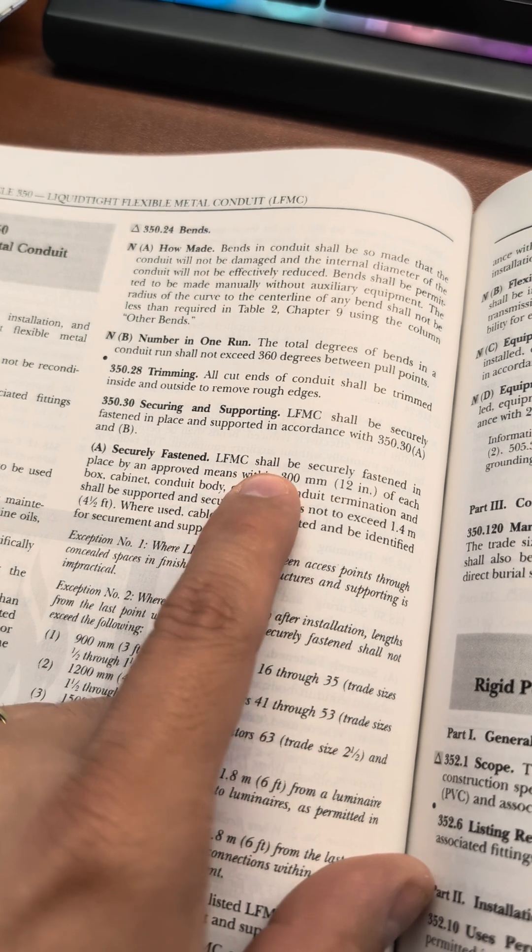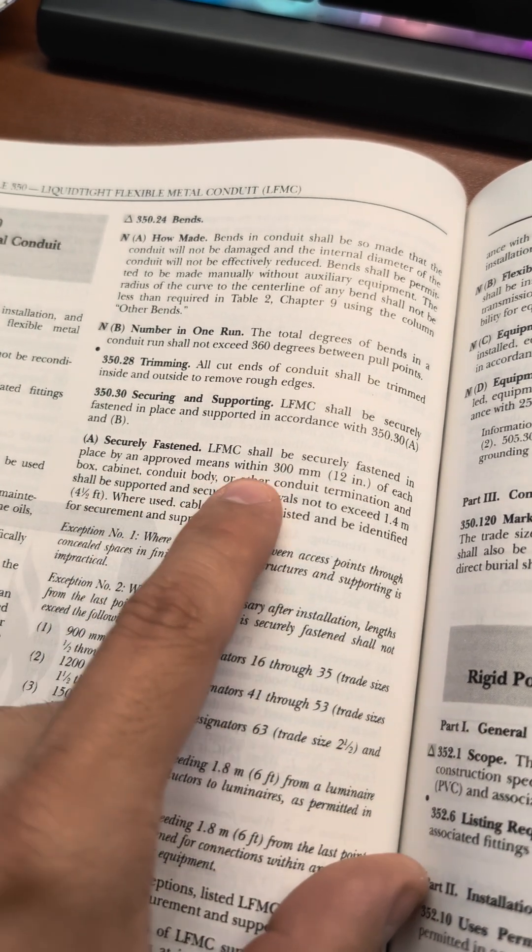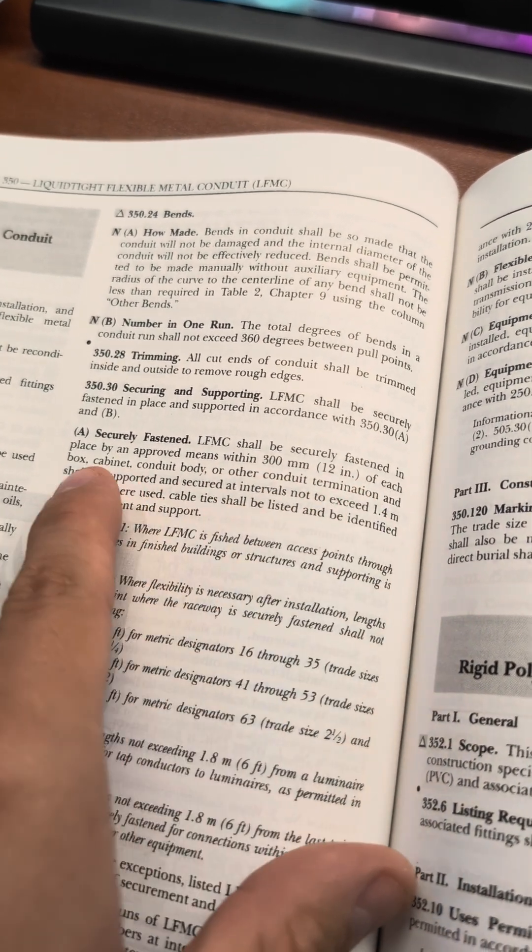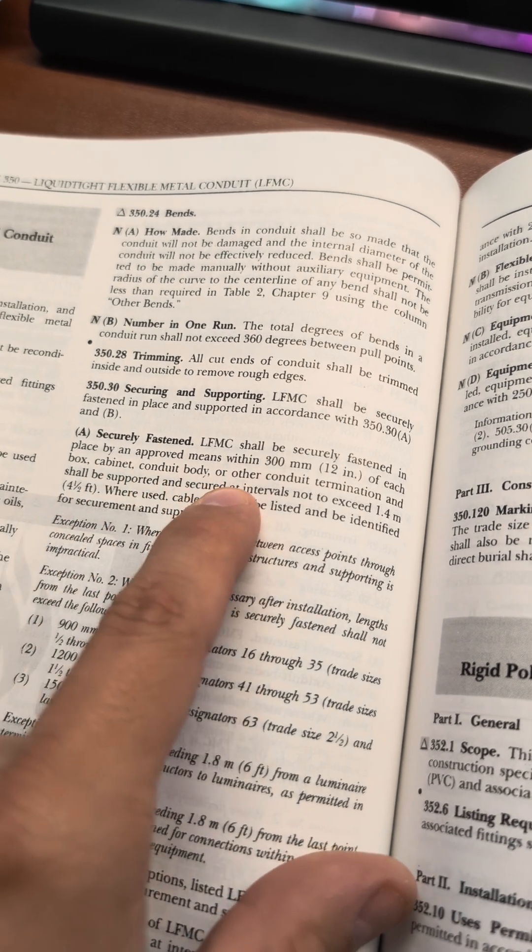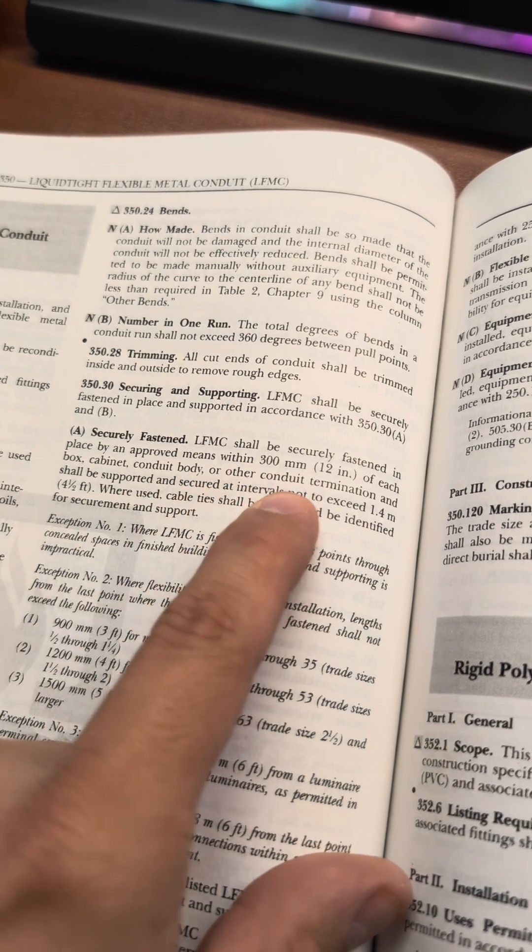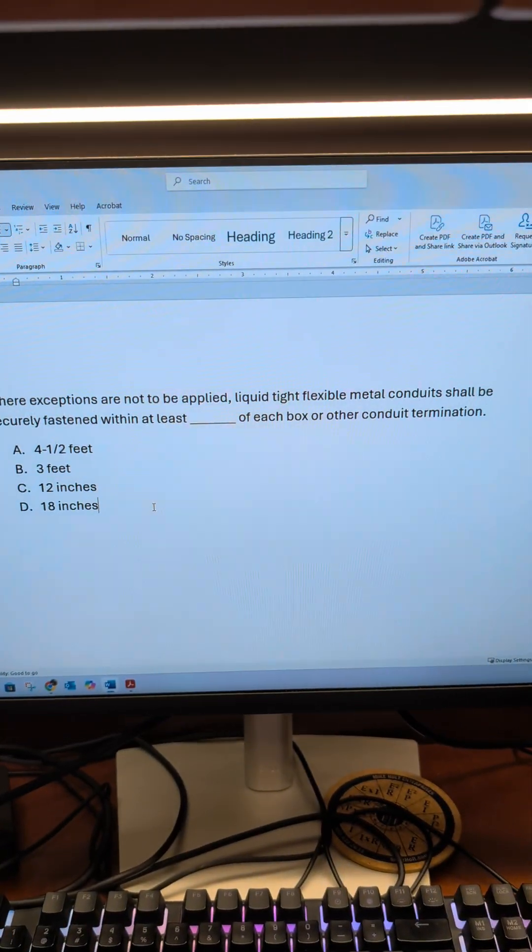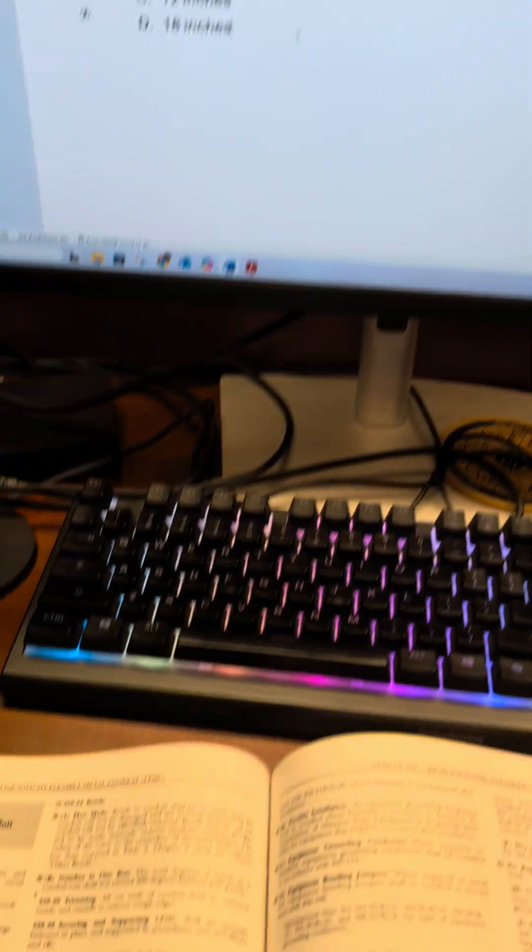LFMC shall be securely fastened in place by approved means within 12 inches of each box, cabinet, conduit body, or other conduit termination. So that answers our question already, 12 inches.